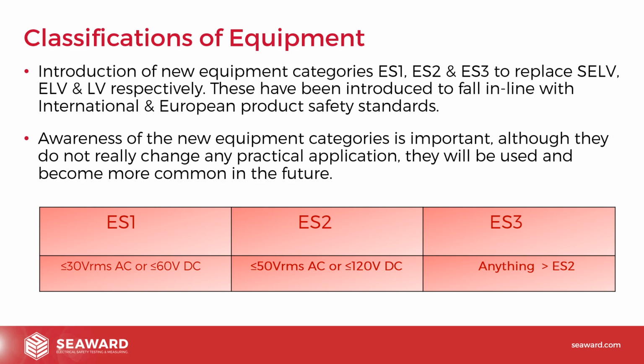So under classifications of equipment, there's been an introduction of new equipment categories, ES1, ES2, ES3, to really replace SELV, ELV, LV, in that order. They don't directly replace these. These are just new terms that are included in the standards, and they need to be defined in here. So you still may have equipment that is SELV or is still specified as SELV, but you'll see these new terms ES1, ES2, ES3 being used mainly in the international and European product safety standards. So awareness of the new equipment categories is important, although they do not really change any practical application. They will be used and become more common in the future.